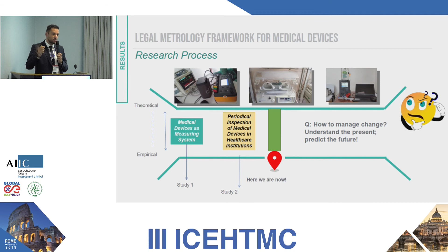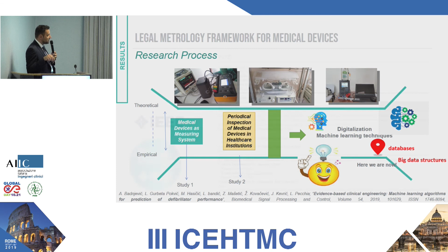And in September of this year, we published one paper called Evidence-Based Clinical Engineering: Machine Learning Algorithms for Prediction of Defibrillator Performances in Elsevier's Biomedical Signal Processing and Control, with all of those concrete cases and real-time testing, again in a healthcare institution. Because we found that there are missing standards in this case, we started at IEEE a new standards series called P2727, which is a standard for general vocabulary for conformity assessment of medical devices with measuring function. Later we started with the number 1 device there, which is a standard for conformity assessment testing of cardiac defibrillators. And we prepared 20 more different standards for different medical devices.